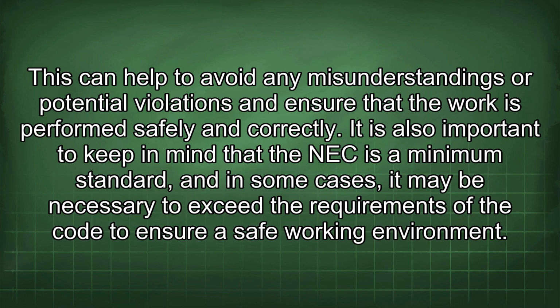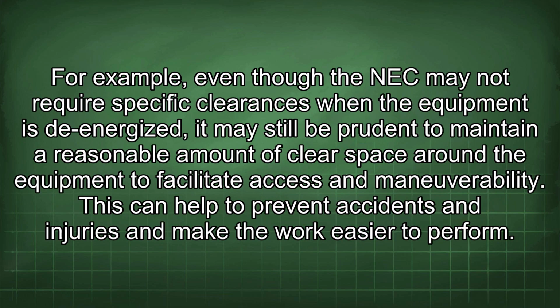It is also important to keep in mind that the NEC is a minimum standard, and in some cases, it may be necessary to exceed the requirements of the code to ensure a safe working environment. For example, even though the NEC may not require specific clearances when the equipment is de-energized, it may still be prudent to maintain a reasonable amount of clear space around the equipment to facilitate access and maneuverability. This can help to prevent accidents and injuries and make the work easier to perform.